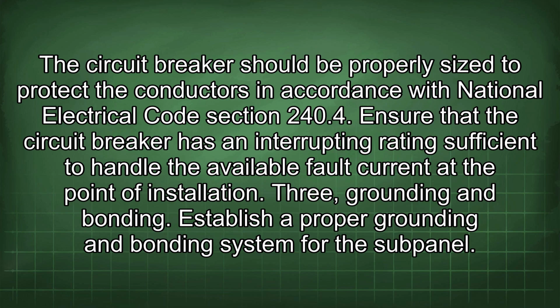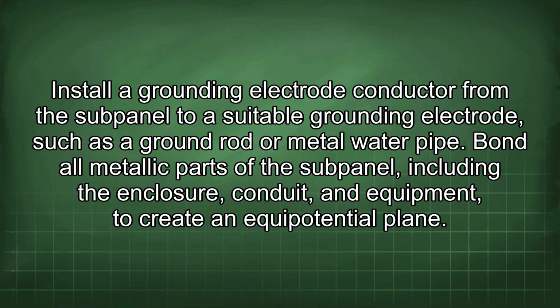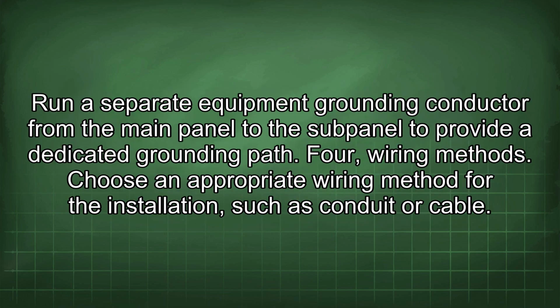3. Grounding and bonding. Establish a proper grounding and bonding system for the subpanel. Install a grounding electrode conductor from the subpanel to a suitable grounding electrode, such as a ground rod or metal water pipe. Bond all metallic parts of the subpanel, including the enclosure, conduit, and equipment, to create an equipotential plane. Run a separate equipment grounding conductor from the main panel to the subpanel to provide a dedicated grounding path.